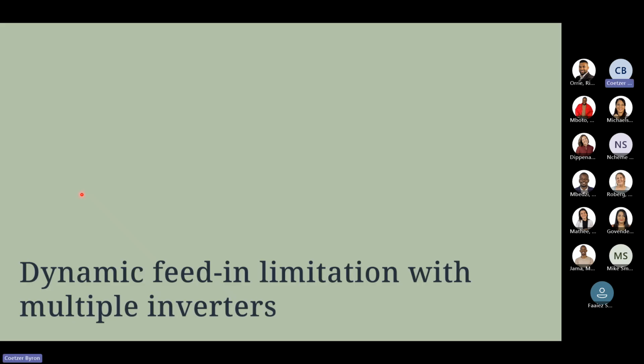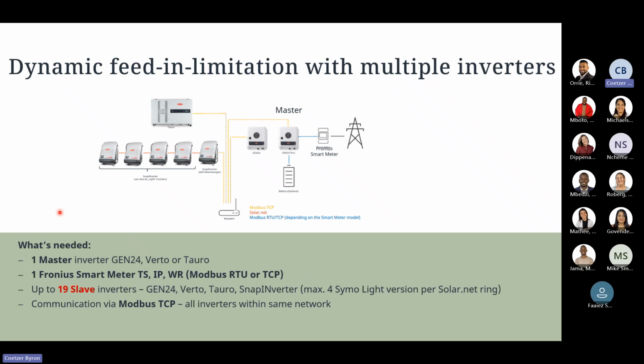Again, if we are making use of the dynamic feed-in limitation with multiple inverters, you will have a dedicated router in the system or an existing one, and we'll need to assign one master in the system. This will either be the Gen 24, Tauro or Verto being the master, as it has a pilot device. If we have a Gen 24 in the system that has a battery, it outranks the Tauro or Verto, for example. So just keep that in mind: if you have a client that has a Gen 24 with a battery and they want to make use of additional units, the master will be the Gen 24 with the battery itself.